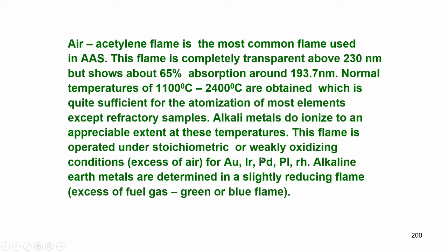Now, air acetylene we had discussed. The air acetylene flame is the most common flame used in atomic absorption spectrometers, and this flame is completely transparent above 230 nanometers, but shows about 65% absorption around 193.7 nanometers.